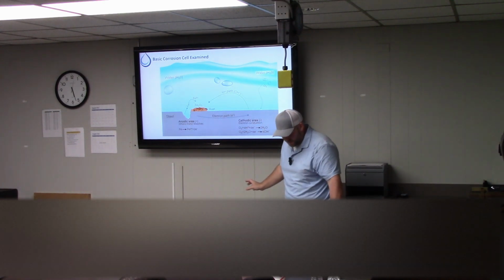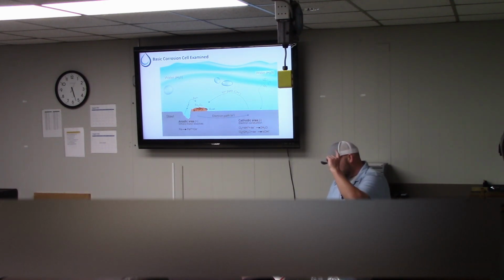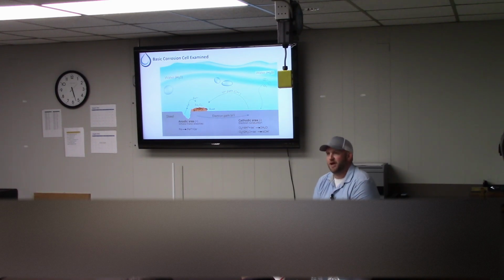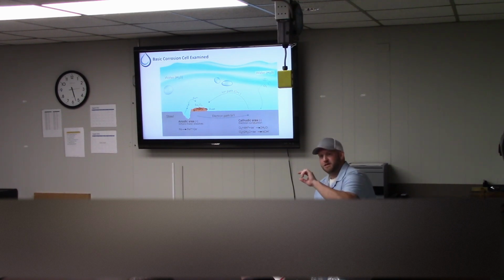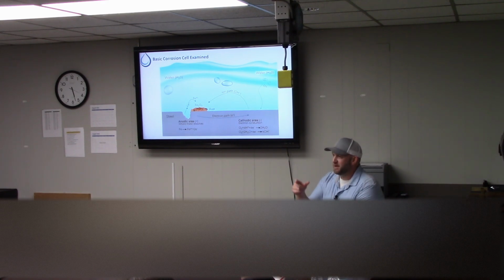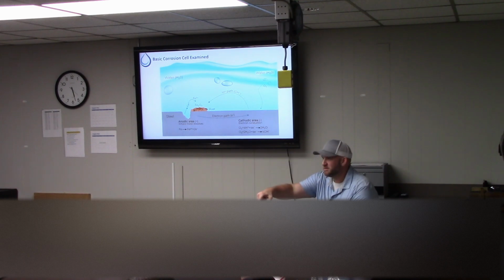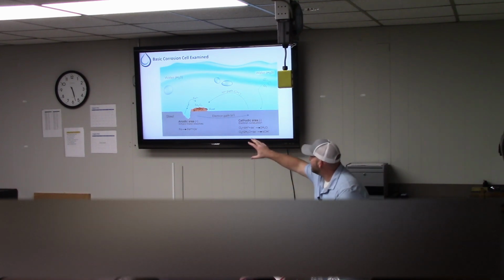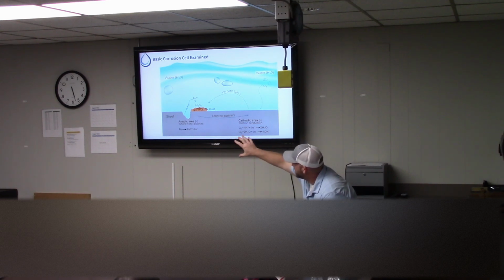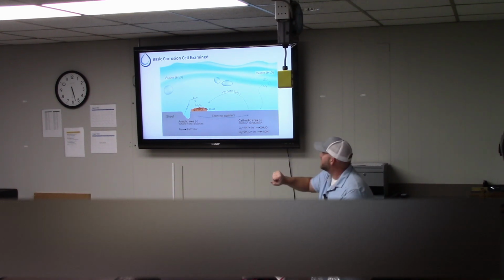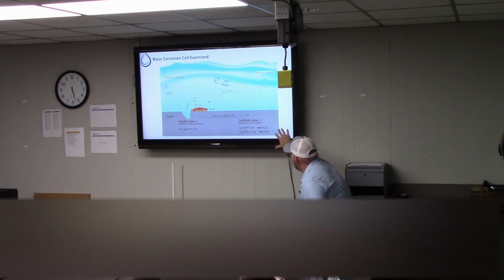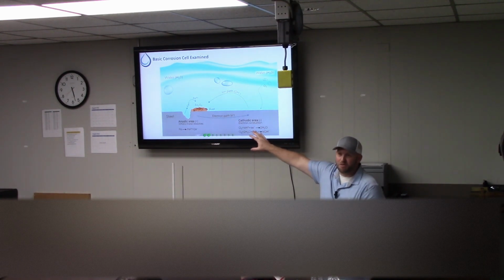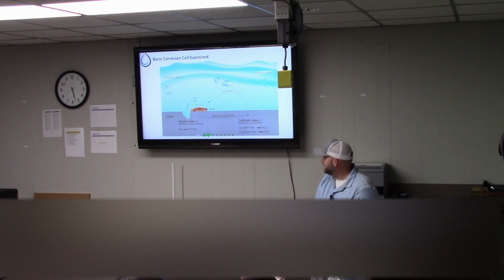At the end of the day, what does this mean? It means, if we think about it, some chillers have sacrificial anodes, right? What is that doing? We're telling the machine that we understand it wants to corrode, and we're hoping that we can bribe it into corroding there. So we put that anode in there because we expect it to exist, and we hope that it sacrifices that piece that we can change out before it attacks our tube bundle, our shell, our channel head, whatever that piece of metal is on the asset that we don't want to have go away.